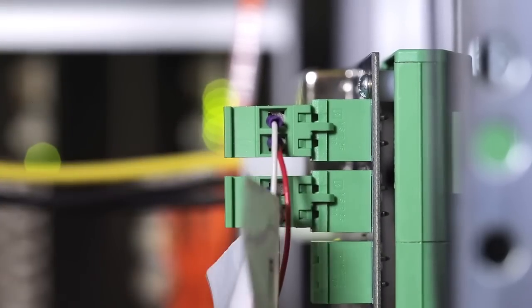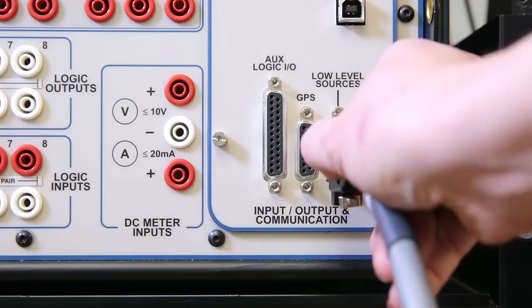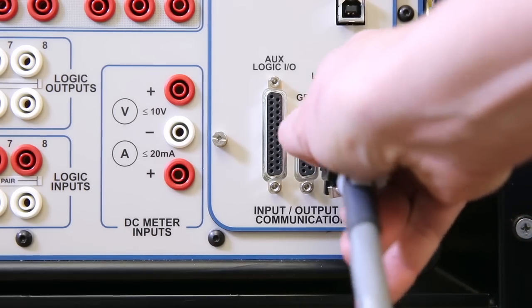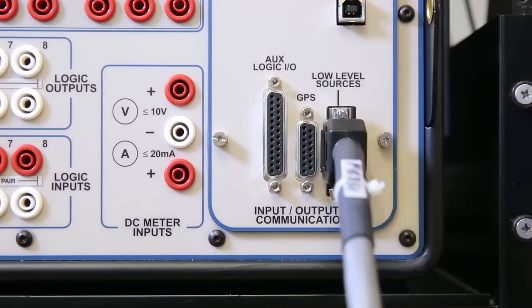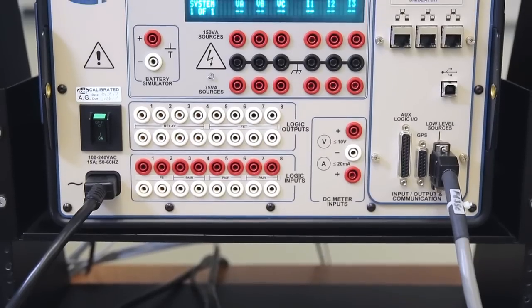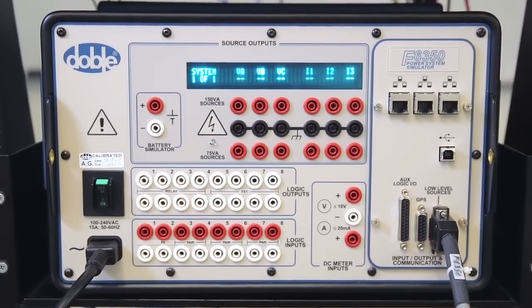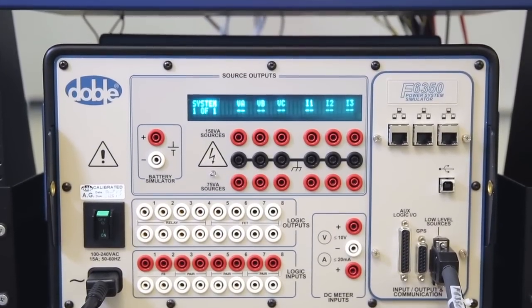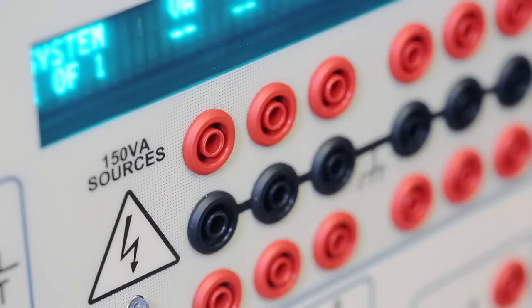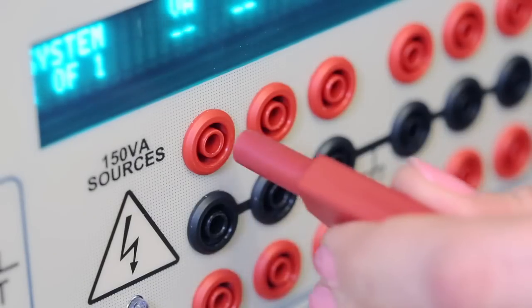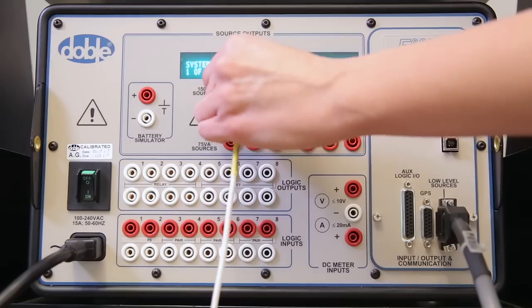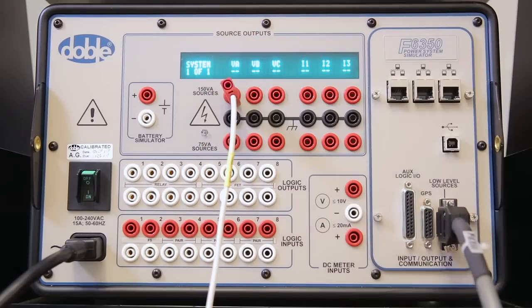The GTAO outputs are connected to the amplifier's input channels and gain levels are carefully set and tested to ensure that the amplifier's output values are as expected. The amplifier outputs are then connected to the protective relay's analog inputs.